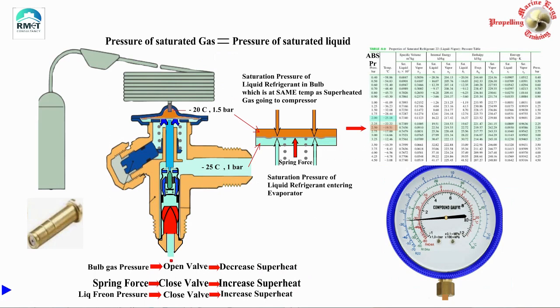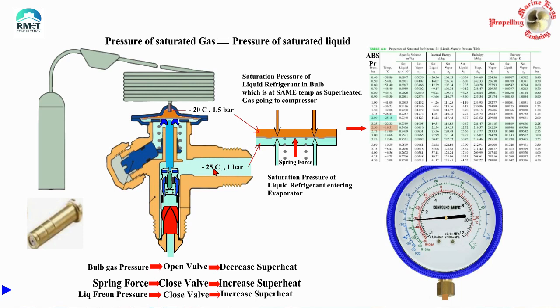Now let us concentrate on the working of this thermostatic expansion valve. What is happening is the liquid from the condenser is entering this expansion valve, and the refrigerant is leaving the expansion valve, dropping its temperature to minus 25 on its way to the evaporator. The pressure of the liquid refrigerant — which is 1 bar, corresponding to minus 25 — is acting on a diaphragm. This pressure, equal to the saturation pressure of the liquid refrigerant at minus 25, is acting on the bottom of the diaphragm.